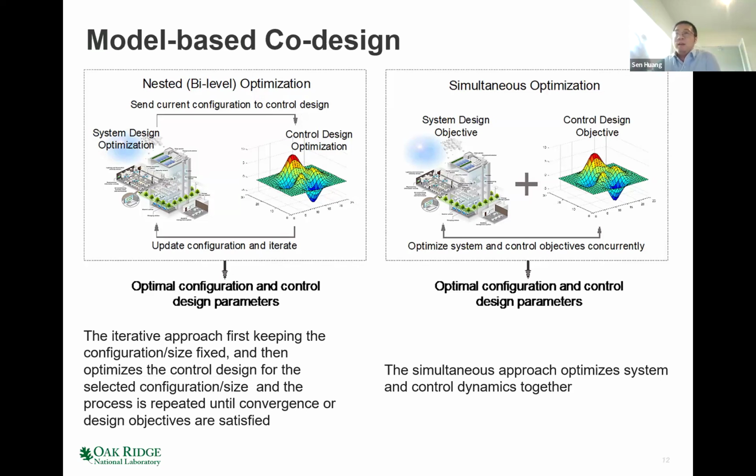For example, if I determine the number of chillers, the model itself will figure out how to map the input signal. For example, if the number of chillers is 2, then based on that input, it can automatically generate the corresponding composite model for chiller 1 and chiller 2 based on the user input. That way, we directly couple the model template with the optimization algorithm, so that once the algorithm returns a particular design, the model will automatically configure itself to accommodate that design, so that we can work together.